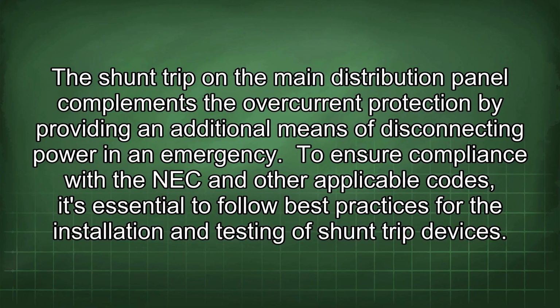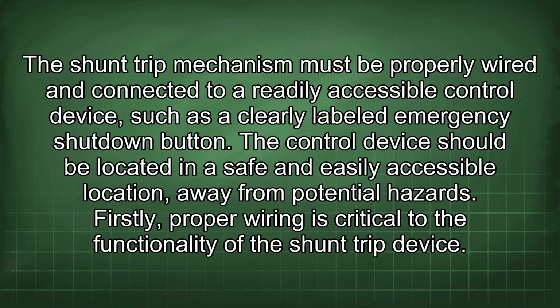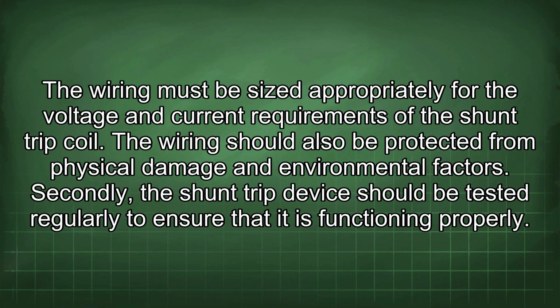To ensure compliance with the NEC and other applicable codes, it's essential to follow best practices for the installation and testing of shunt trip devices. The shunt trip mechanism must be properly wired and connected to a readily accessible control device, such as a clearly labeled emergency shutdown button. The control device should be located in a safe and easily accessible location away from potential hazards. Firstly, proper wiring is critical to the functionality of the shunt trip device. The wiring must be sized appropriately for the voltage and current requirements of the shunt trip coil. The wiring should also be protected from physical damage and environmental factors.